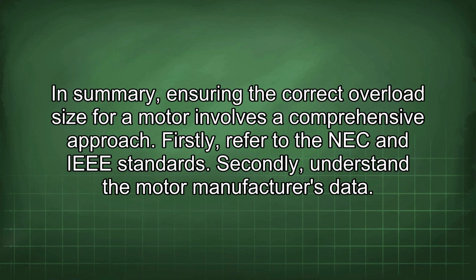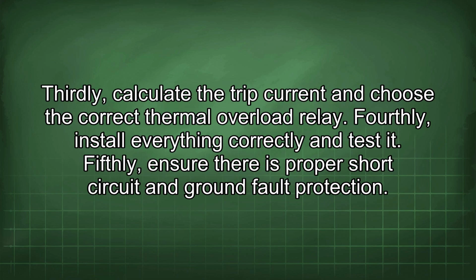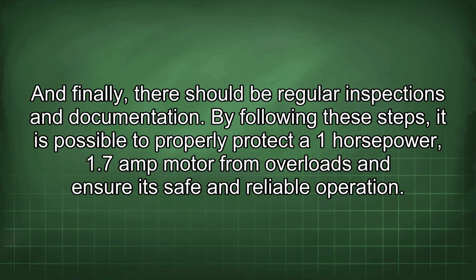In summary, ensuring the correct overload size for a motor involves a comprehensive approach. Firstly, refer to the NEC and IEEE standards. Secondly, understand the motor manufacturer's data. Thirdly, calculate the trip current and choose the correct thermal overload relay. Fourthly, install everything correctly and test it. Fifthly, ensure there is proper short circuit and ground fault protection. And finally, there should be regular inspections and documentation.